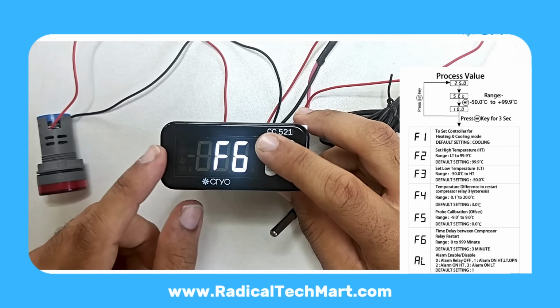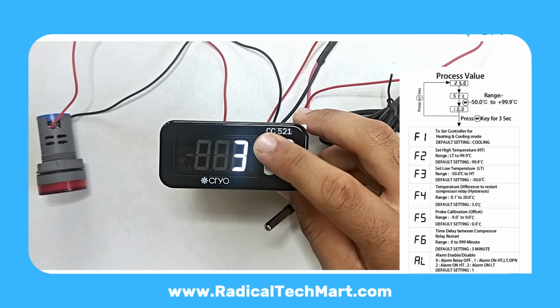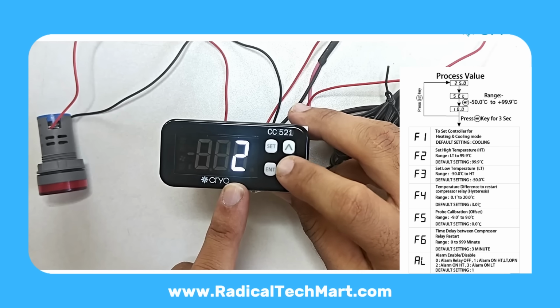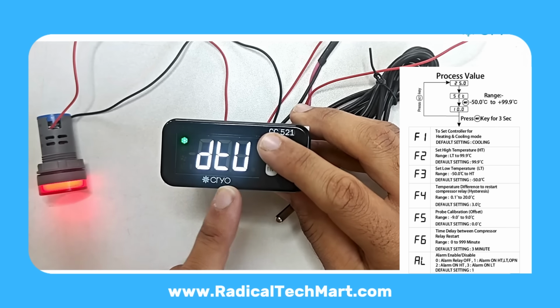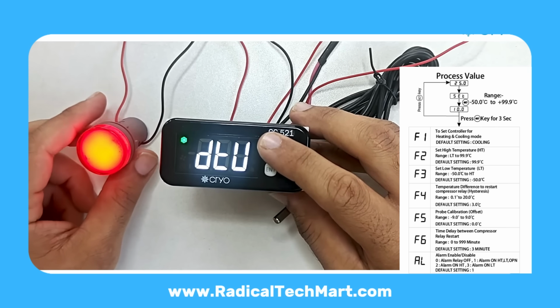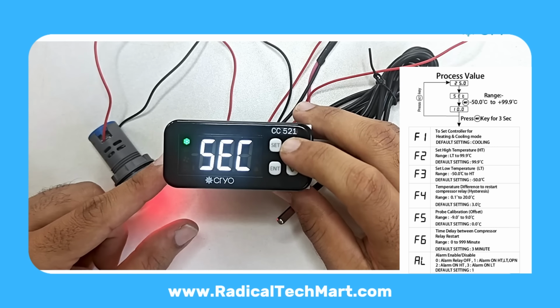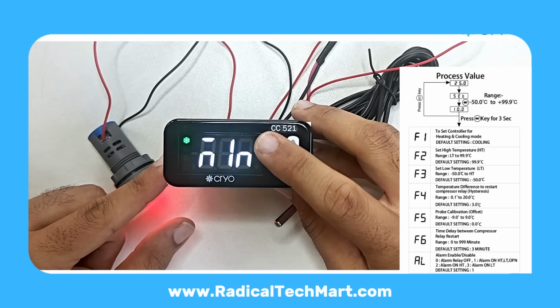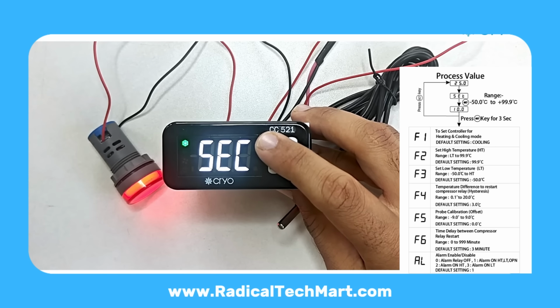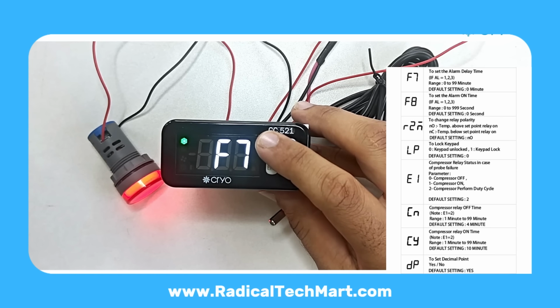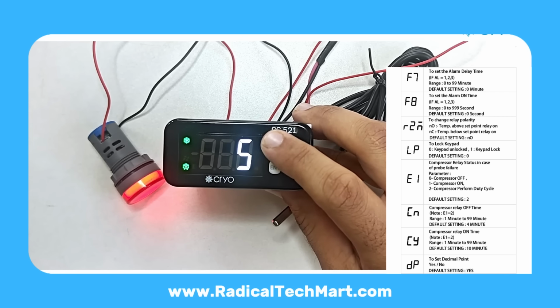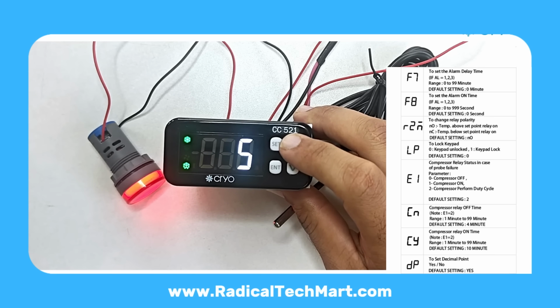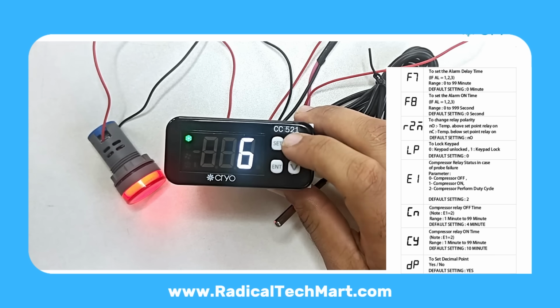This defines the delay between power on and compressor start, default 3 minutes. You can reduce it to 0 if you want an instant start. DT Defrost Time Unit. Choose whether the defrost time is expressed in minutes or seconds. F7 Defrost Duration. Set how long each defrost cycle should run, example 10 minutes.